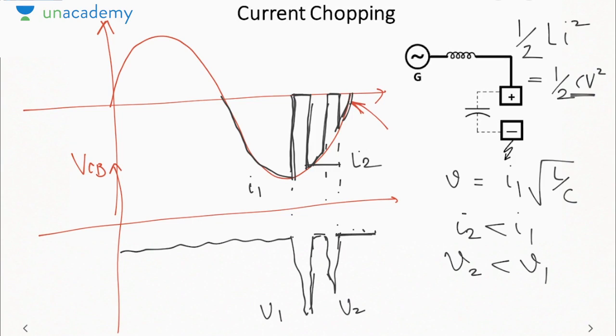How to do that? We will introduce resistance switching. Why? Because when resistance is connected, this electromagnetic energy will be converted into heat plus electrostatic energy, due to which the electrostatic energy reduces and the voltage across the plates of the circuit breaker also reduces. Because in the resistance there will be some current and some heat produced, all that energy will be supplied by the electromagnetic energy. So now the electrostatic energy is not equal to the electromagnetic energy, but electromagnetic minus heat dissipated. So the energy reduces, hence the voltage also reduces. So resistance switching is used to avoid the current chopping phenomenon.